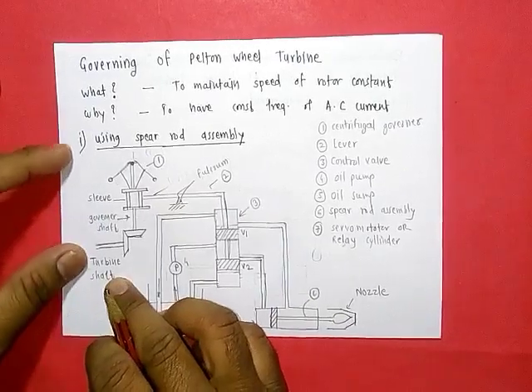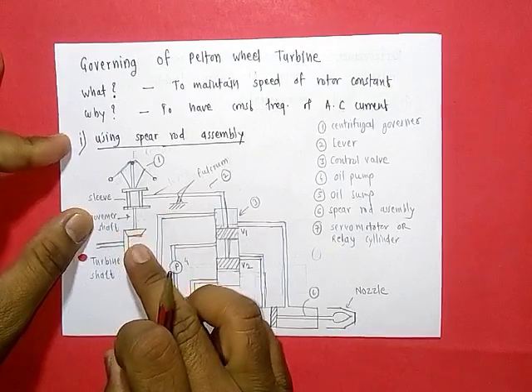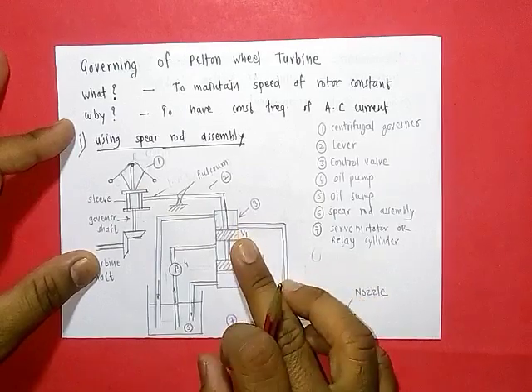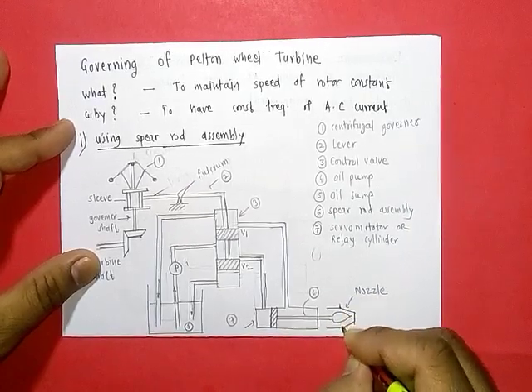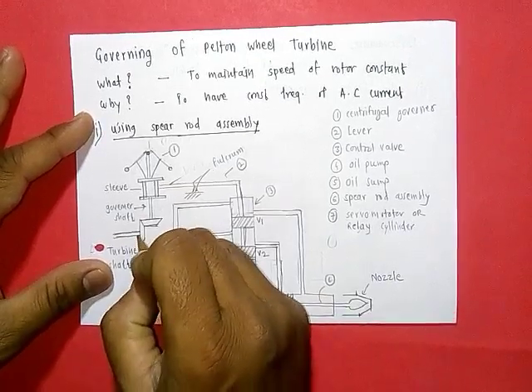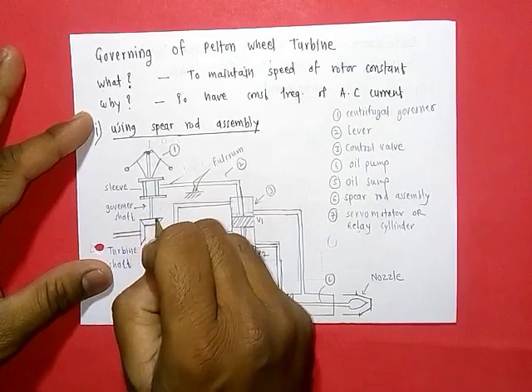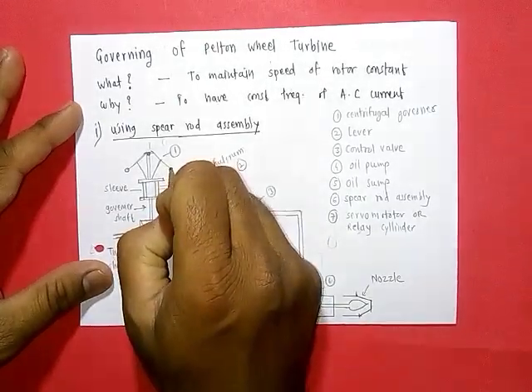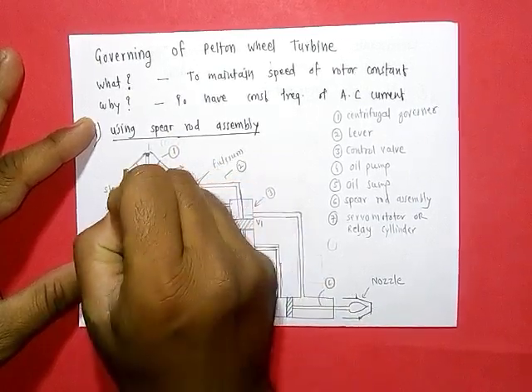The turbine shaft is geared with the governor shaft. When the turbine operates at rated speed, both valves are closed and the spear rod is in its normal position. When the speed of the turbine shaft increases, the governor shaft speed also increases, increasing centrifugal force, causing the governor balls to move outward.